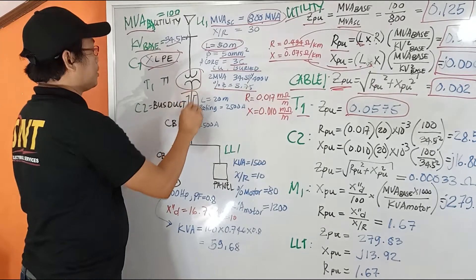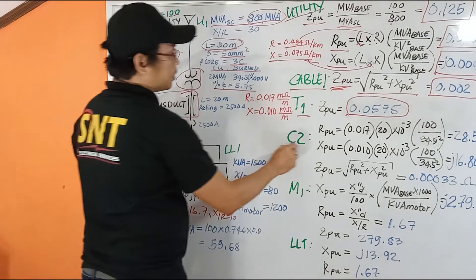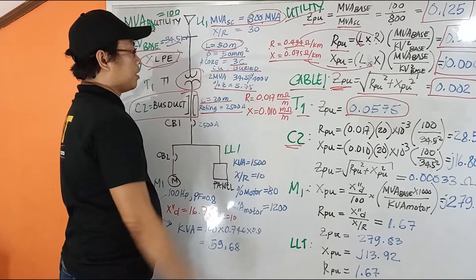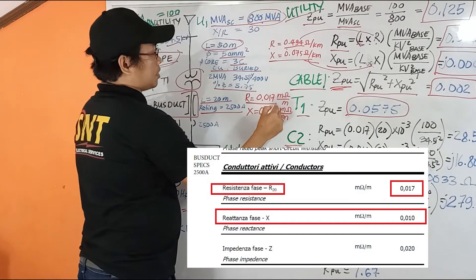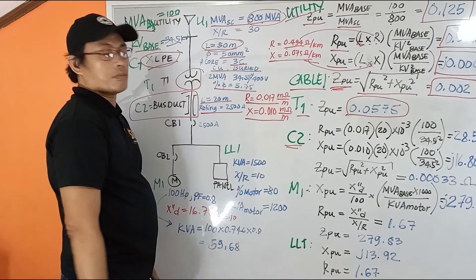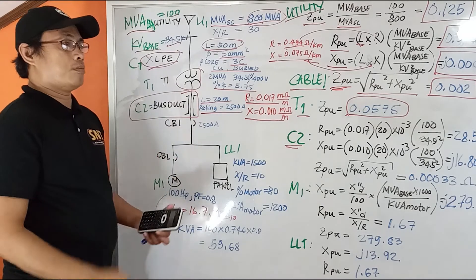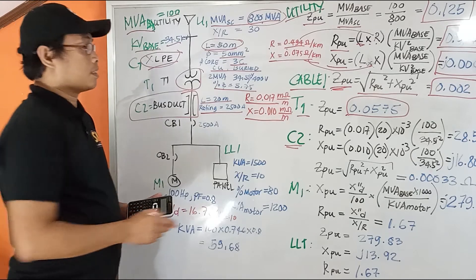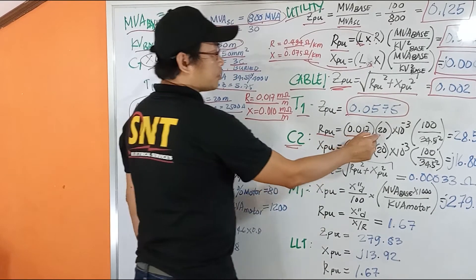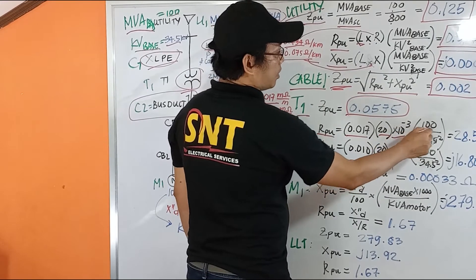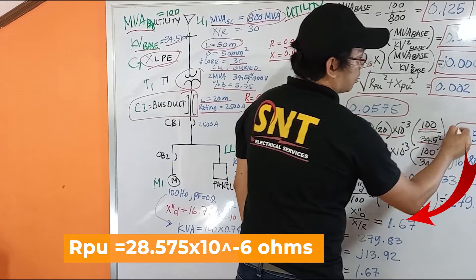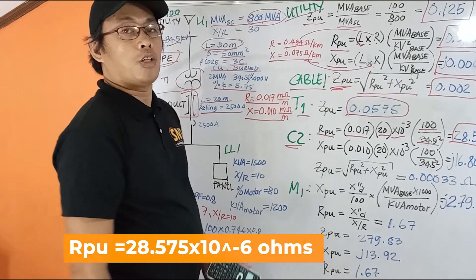So then our bus duct here, which is our cable number two. After getting all the information, which is given the length as 20 meters, the rating at 2,500 ampere, it was given the resistance at 0.017 milli ohm per meter and the reactance at 0.010 milli ohm per meter. So the bus dock is considered zero impedance. So let's calculate that. Resistance per unit: 0.017 times the 20 meters times 10 to the negative 3. Very small.